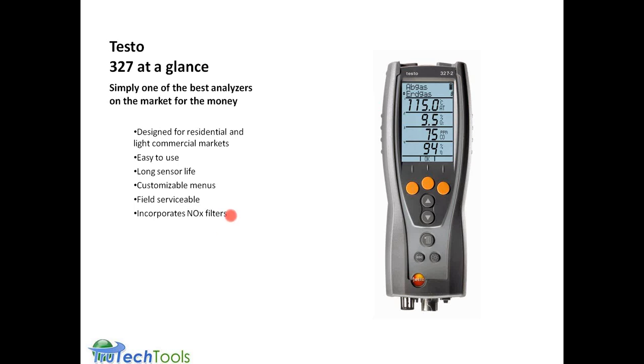Testo has incorporated an onboard NOx filter right into the sensor. That will make the Testo readings look lower to an uncompensated or an uncorrected meter. But when you're out to measure carbon monoxide, you're out to measure CO, not to measure CO and an unknown concentration of NOx that goes along with it. So it's important to have that. Testo's built it in as a filter into the front of the CO sensor.